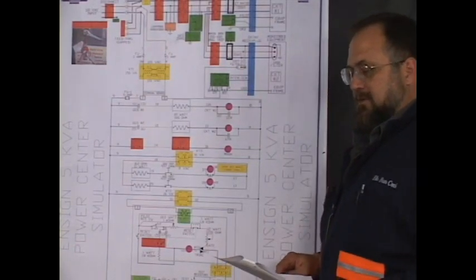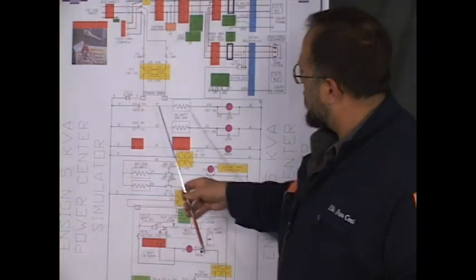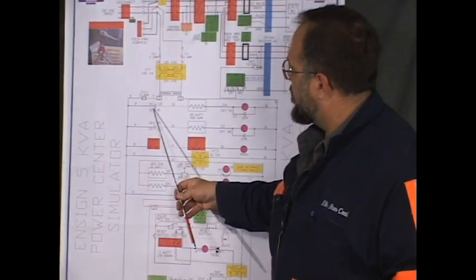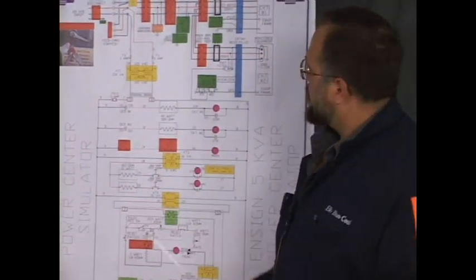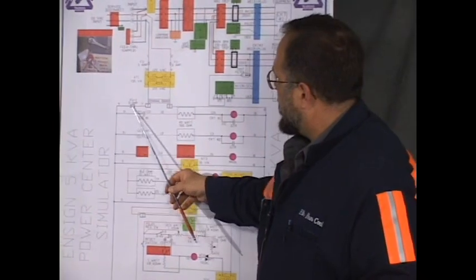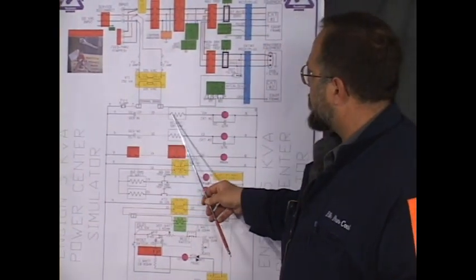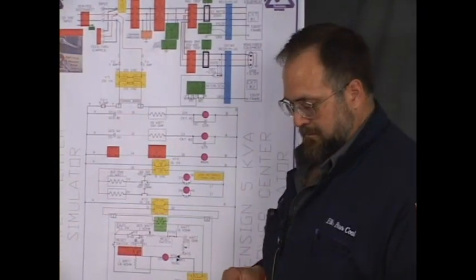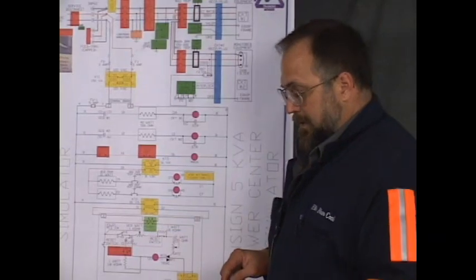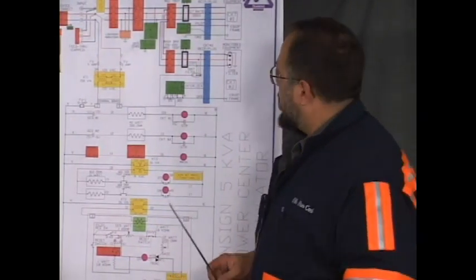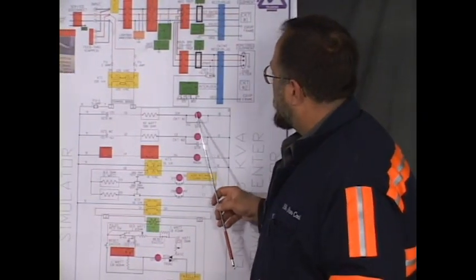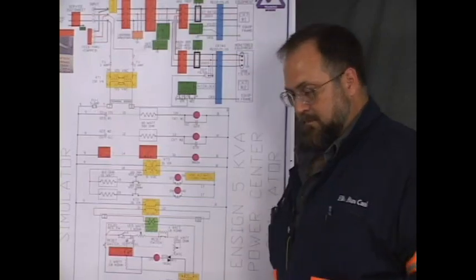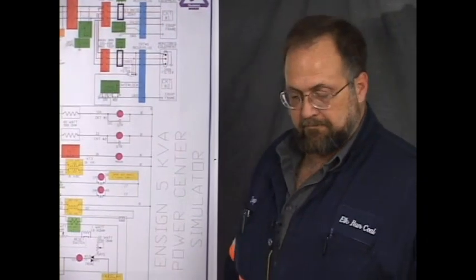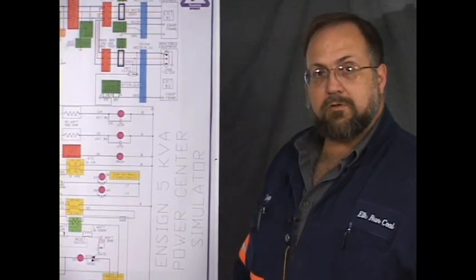GCS1 contact is closed. It says the monitor is satisfied. That contact is closed, so that's stating it's connected all the way through there. And it says the UV coil is not open. UV will pick up. Proper control voltage present. GCS1 contact closed. UV coil is not open.